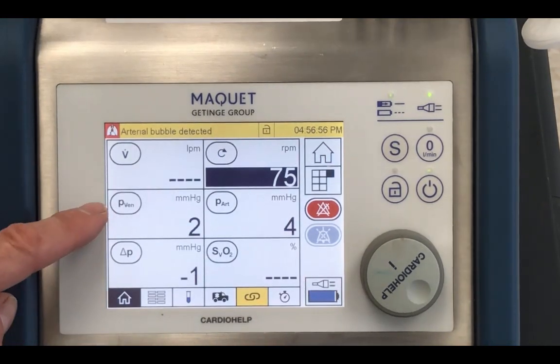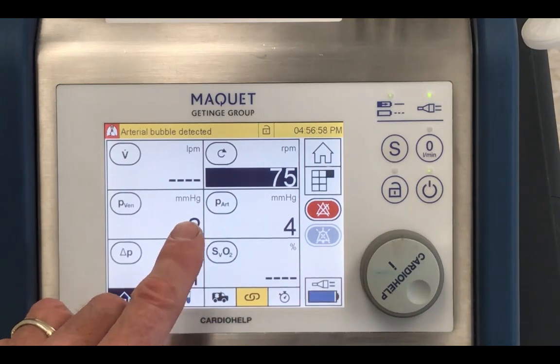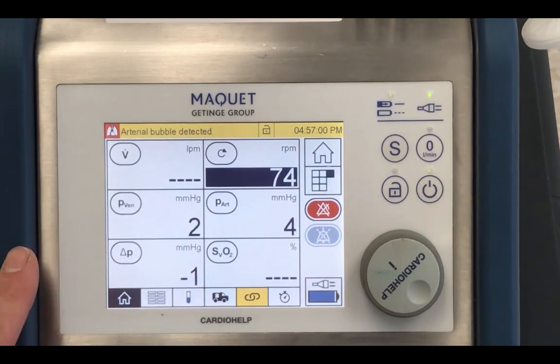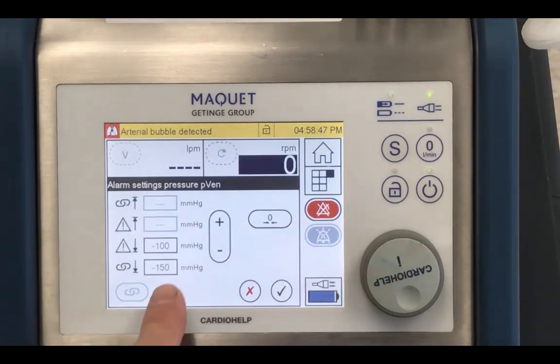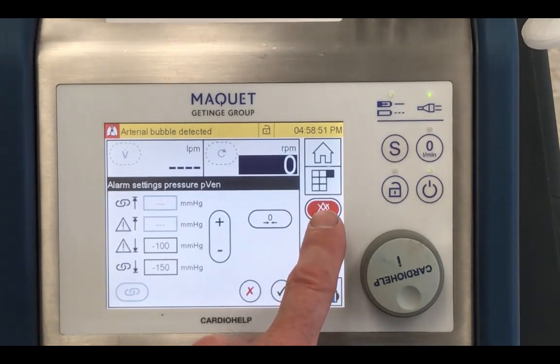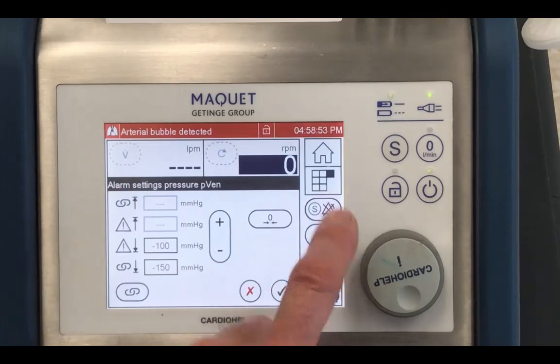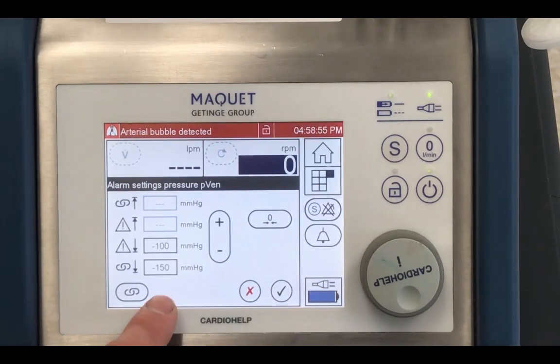And here we are, venous line pressure. There's a number in there, so it must be getting data. So it's going to be the second thing. You can't change these interventions when you're in global override. So let's, for a moment, take it out of global override. Just need to touch this once. All right, start getting some alarms. And you see that this is not grayed out anymore.